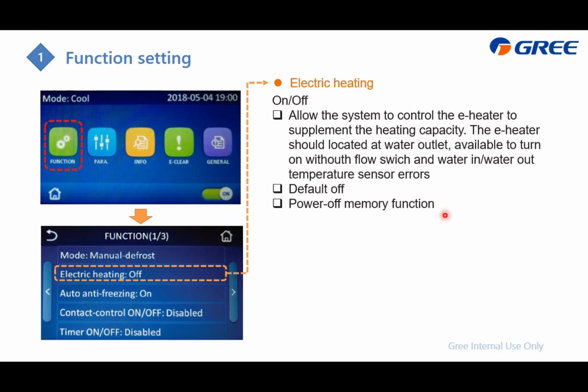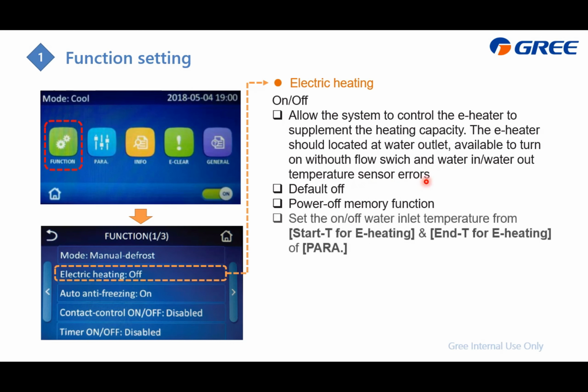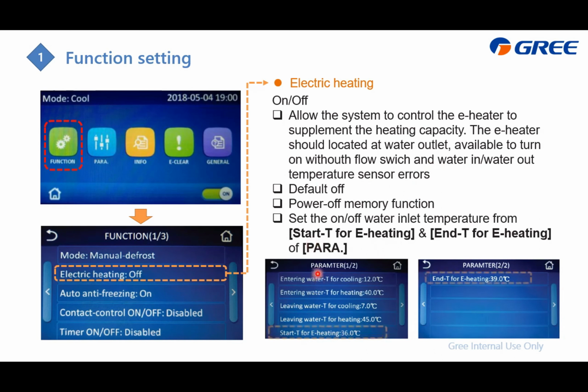Next is the e-heater control. What you can set here is turn on or turn off, and this just allows the chiller to control the e-heater. It is not directly turned on, it depends on the condition: if there is no flow switch or water in and out temperature sensor error, then it is allowed to turn on. This allow is not turned on directly because it is related to the parameter setting, which I will detail later. This is the start-up temperature for the e-heater, and this is the end temperature of the water temperature for the e-heater.